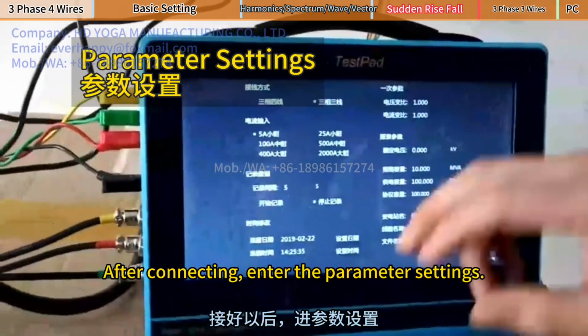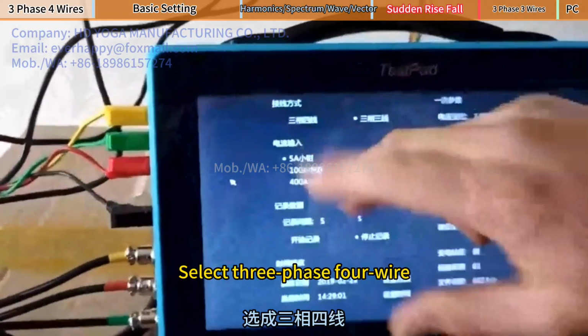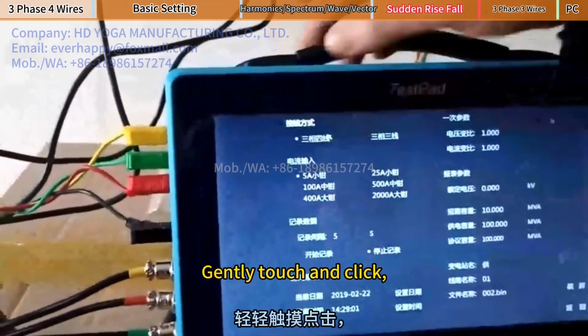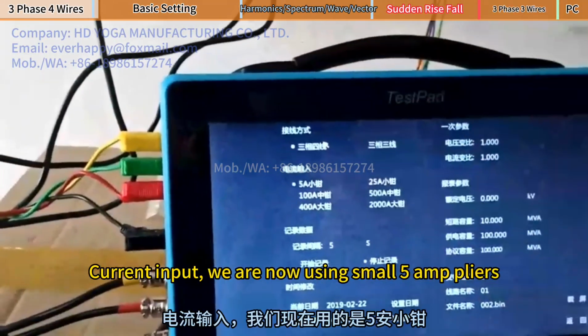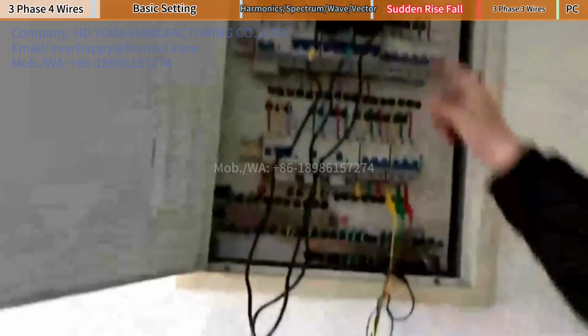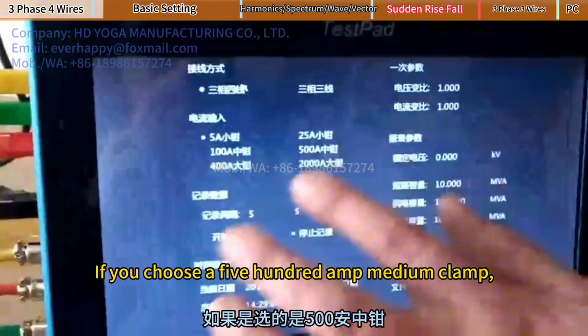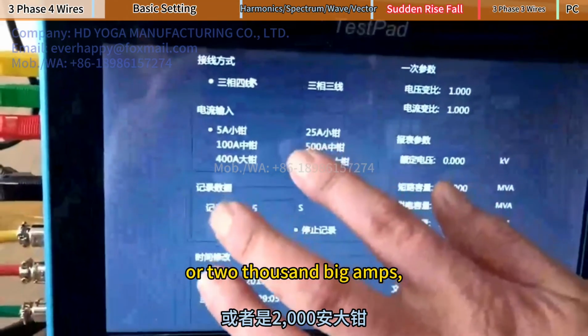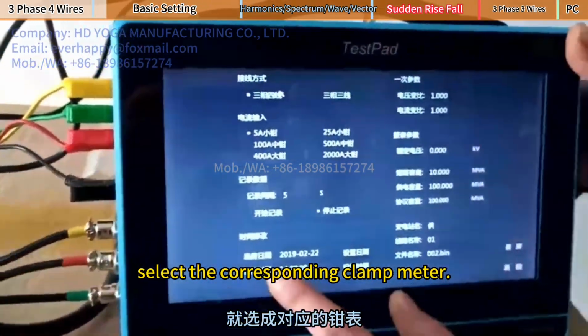After connecting, enter the parameter settings. Select 3-phase 4-wire. Gently touch and click. Current input. We are now using the small 5 amp clamp. Select 5 amp small clamp. If you choose a 500 amp medium clamp or a 2000 amp big clamp, select the corresponding clamp meter.